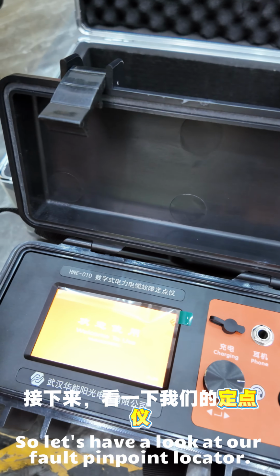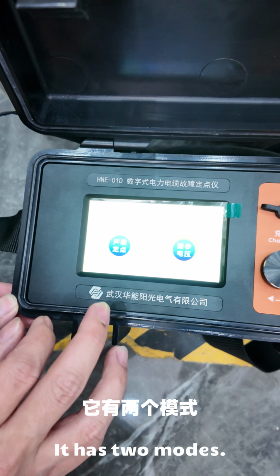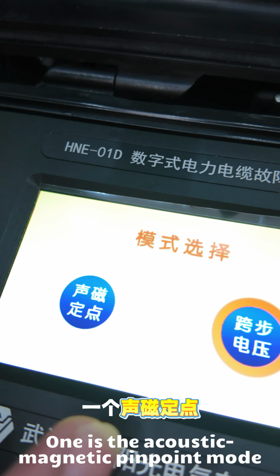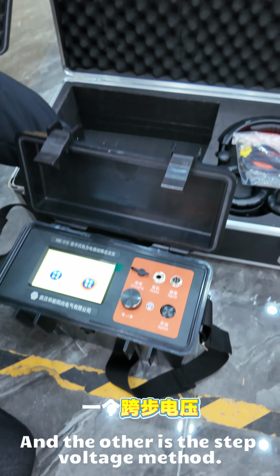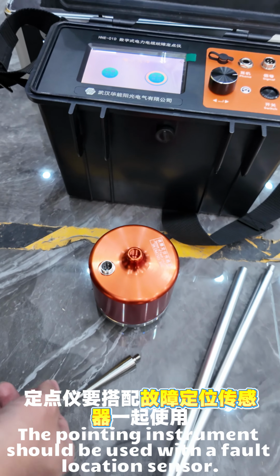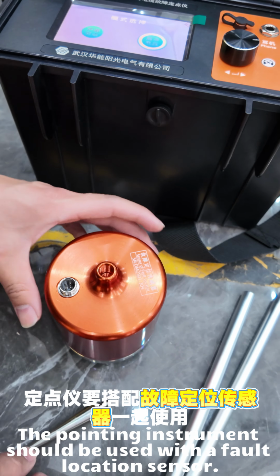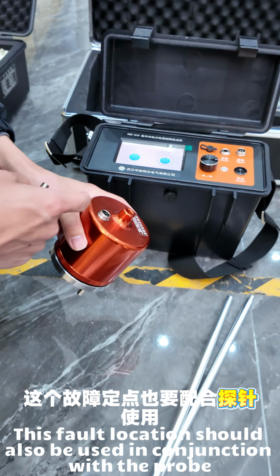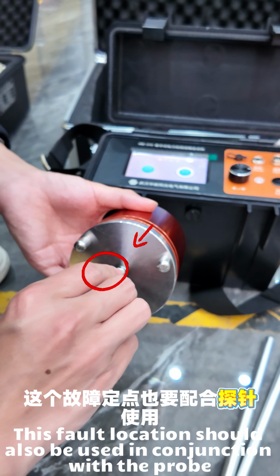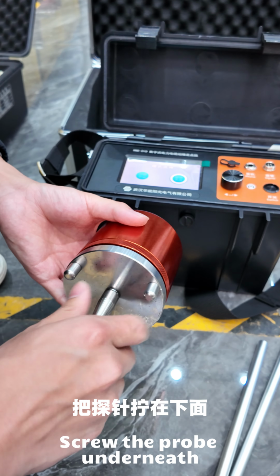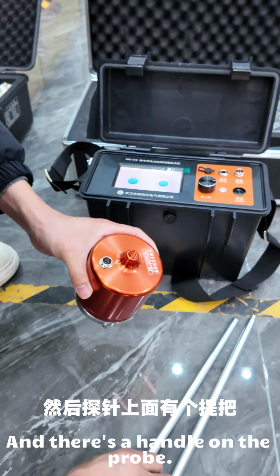So let's have a look at our fault pinpoint locator. It has 2 modes. One is the acoustic-magnetic pinpoint mode, and the other is the step voltage method. The pointing instrument should be used with a fault location sensor. This fault location sensor should also be used in conjunction with the probe. Screw the probe underneath, and there's a handle on the probe.